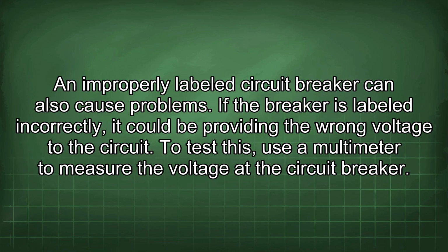circuit. An improperly labeled circuit breaker can also cause problems. If the breaker is labeled incorrectly, it could be providing the wrong voltage to the circuit. To test this, use a multimeter to measure the voltage at the circuit breaker.